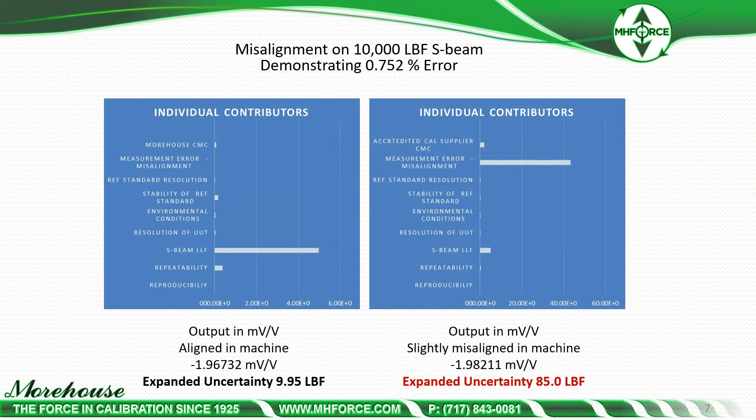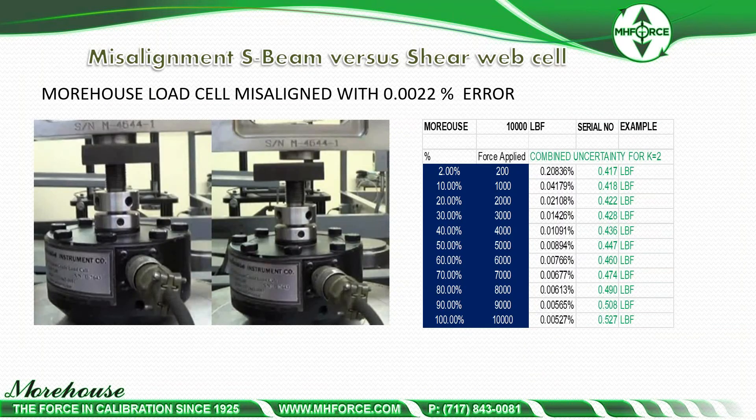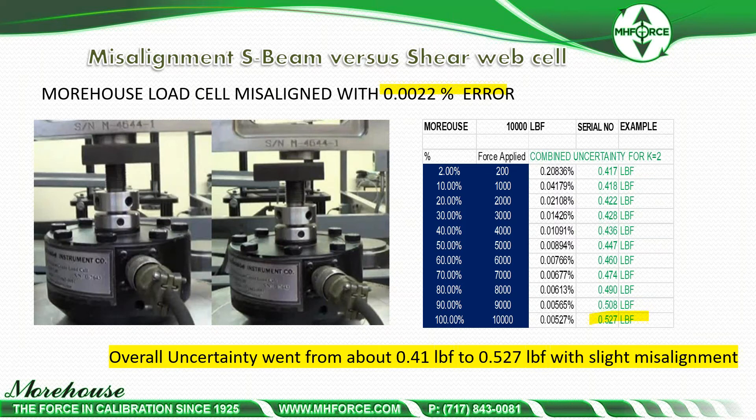Looking at this graphically in terms of contributors: when the S-beam is aligned in the machine and we do an ASTM E74 calibration, the S-beam LLF is the largest individual contributor. Whereas when it's slightly misaligned, the misalignment error is very dominant — 9.95 pounds expanded uncertainty when aligned versus 85.0 when misaligned. Now, if we look at a shear web load cell and do the same thing, even with the cell greatly misaligned, the error is about 0.0022%, or 22 parts per million — about half a pound at 10,000 pounds. The overall uncertainty on a shear web cell goes from 0.41 LBF to 0.527 LBF with slight misalignment.